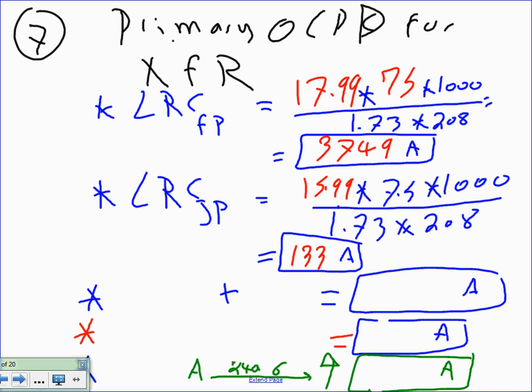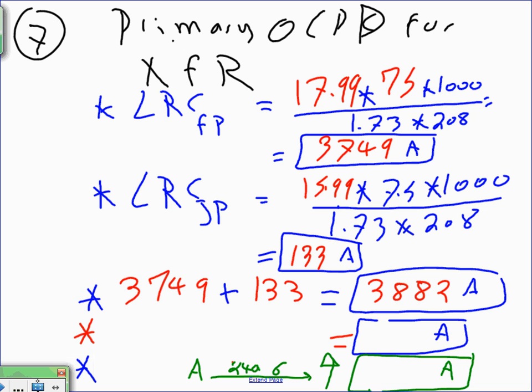Up to this time, guys, it's nothing, no gimmicks. Up to 3, then we add them up. 3,749, add it to 133, and that will get me 3,882 amps, right? Add them up, locked rotor. This is the step that's kind of interesting. So we add them up in step number 3, guys, straightforward. Step number 4, when you add them up, then you take the 3,882. Now, Nick, I want you to wake up. I know you're up. Up to this point, guys, we are on the secondary. These 3,882 are amps on the secondary.